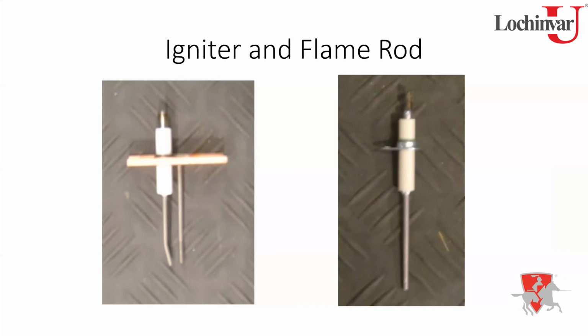Now, once you do that, you've got your flame rod sitting over here doing its thing, looking for a flame signal. Now, the control module, unfortunately, doesn't tell you what that signal is. However, if you wanted to put a microamp meter in series with the flame rod to the control module and look at that flame signal, you could do that if you wish. Typical flame signals are probably going to be anywhere between 4 to 8 microamps. Right. You might see them go higher, and if it goes higher, that's fine. It's not a big deal.